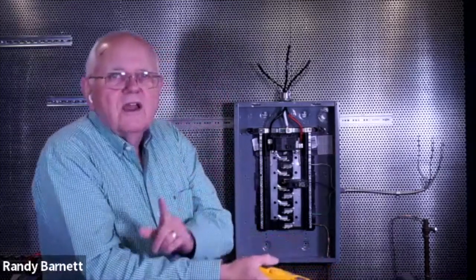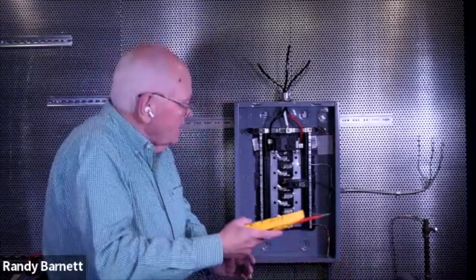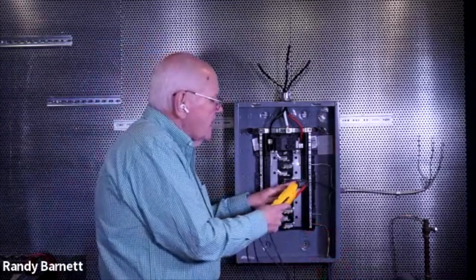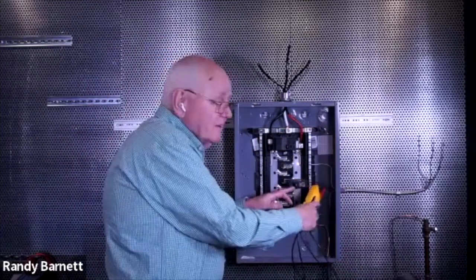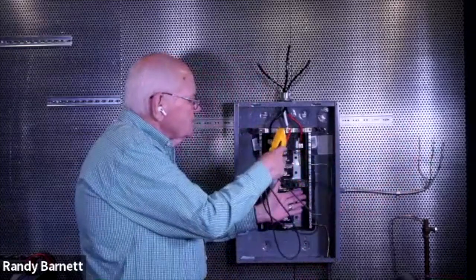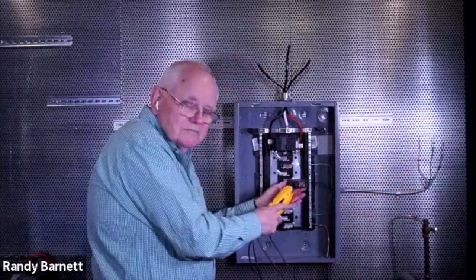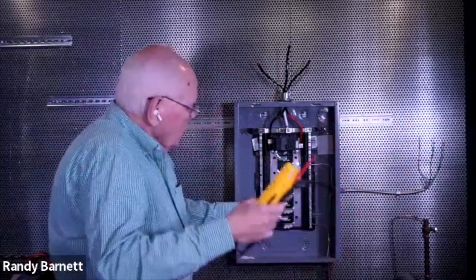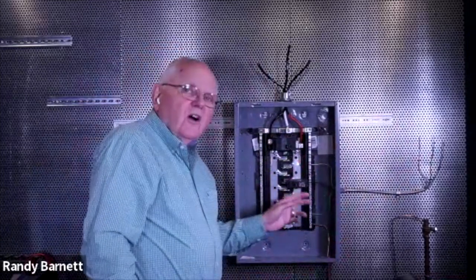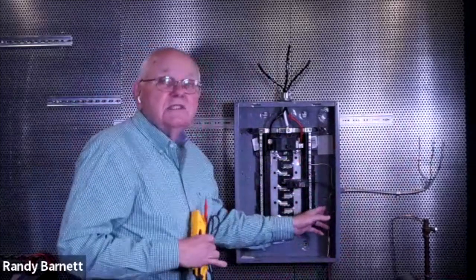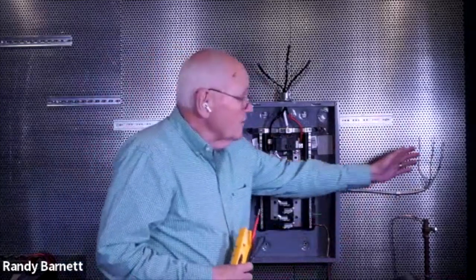Now, if I get enough ground fault current, I can have some pretty serious ground faults. If I get enough ground fault current, what's going to happen? The current's going to flow out the ungrounded conductor, flow into the metal frame of the equipment, return to the green wire and back to the source, and this circuit breaker is going to trip. Because basically I got a short circuit into the metal frame of my equipment. That would be pretty common when I have a ground fault. So anyway, I'm going to trip the circuit breaker and clear the fault. That's what I want that green wire to do. It's going to give me some protection. It's going to prevent current flowing through my body and into the ground. That's a good deal, huh?